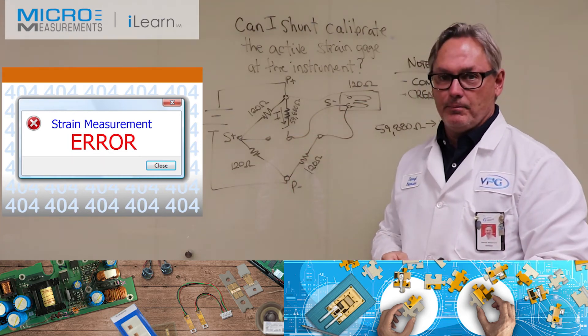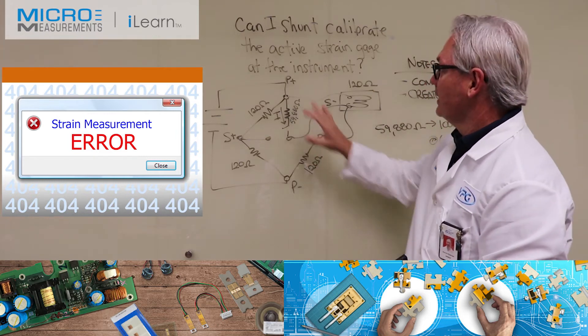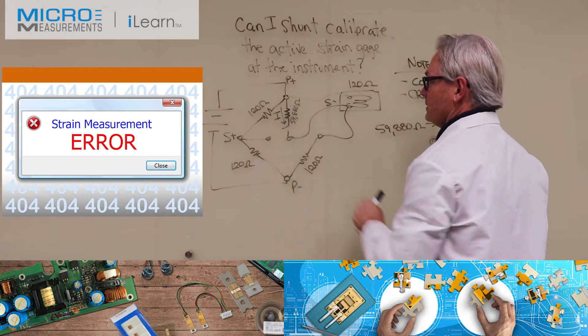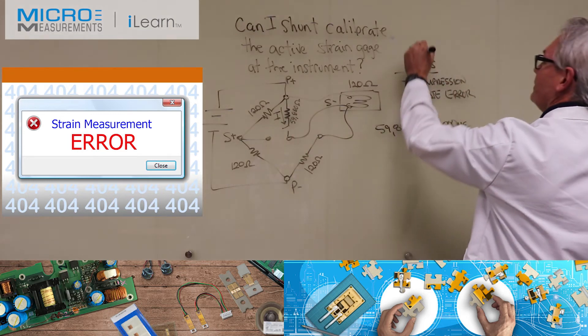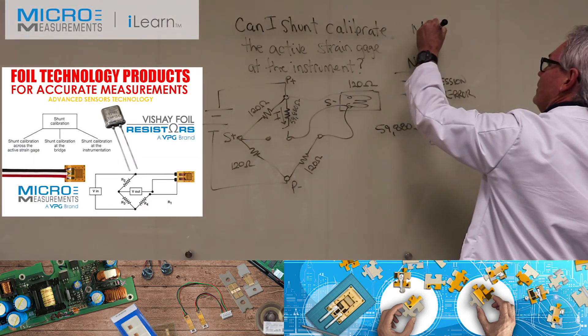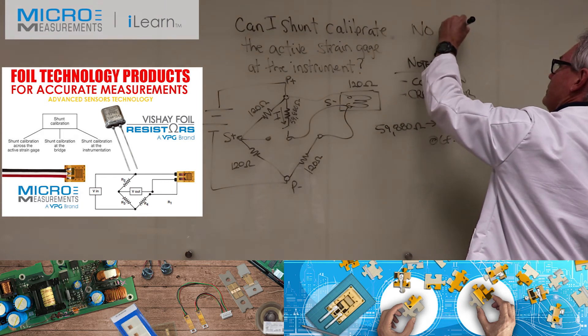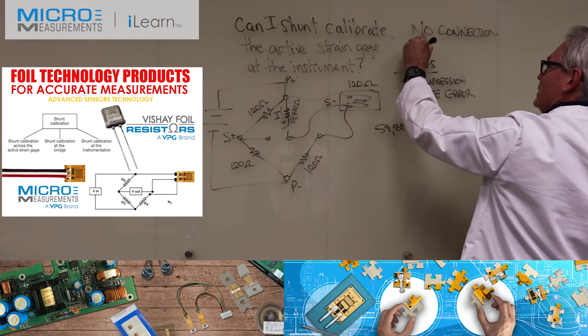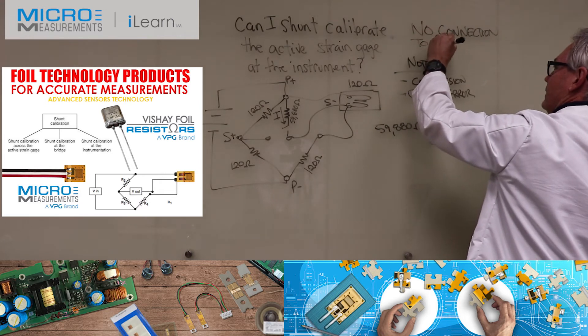That current - if you think about it, you have a switch where you're dropping it in place. You put the resistor, you put a switch, you close it, and now it's only present during the calibration, not there while your strain gauge is active and you're trying to make measurements. So it creates a change that's only present during the calibration, not present during the active measurements. That current draw on this signal lead is a problem. So we would say, can you shunt calibrate the active strain gauge? At this location we would say no. No connection to signal leads - we don't like that.